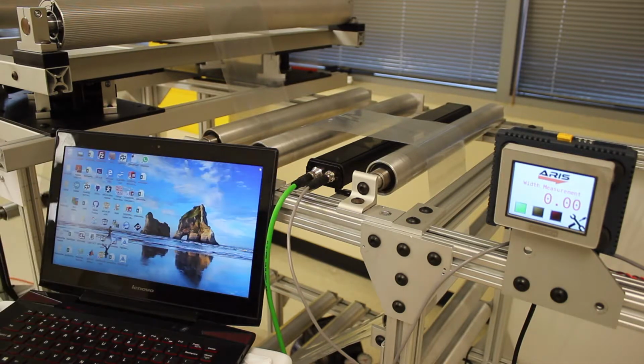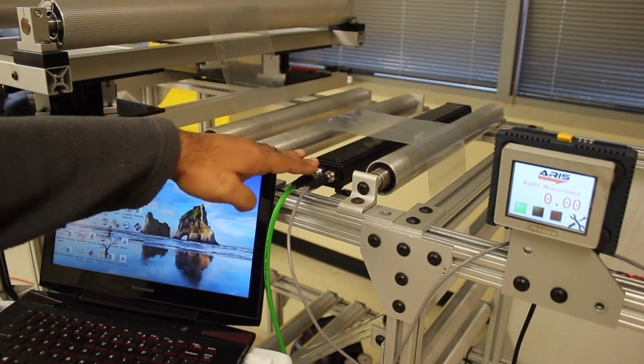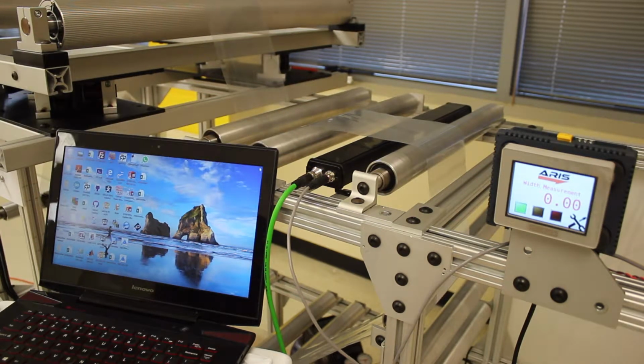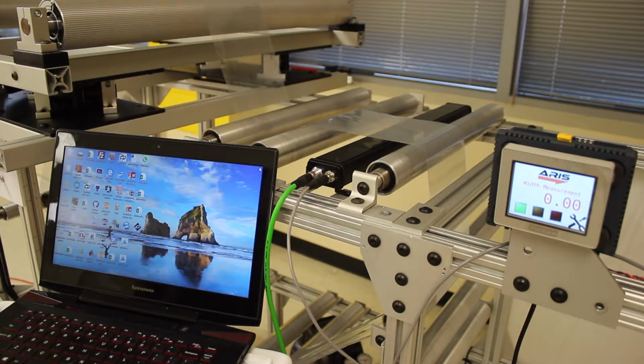This sensor is actually connected to Ethernet IP, so you can connect it to a PLC like this, or we also have a web browser interface on the computer that you can connect to. So the main thing here is how far the sensor is from the web. Right now we've installed it at about 5 millimeters from there. That's the optimal distance that we recommend.